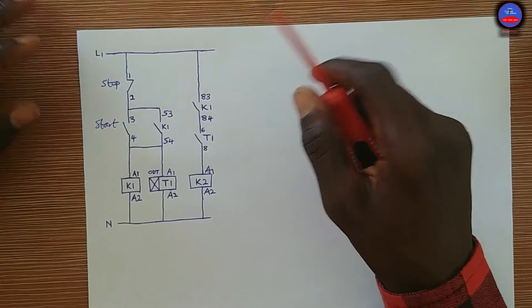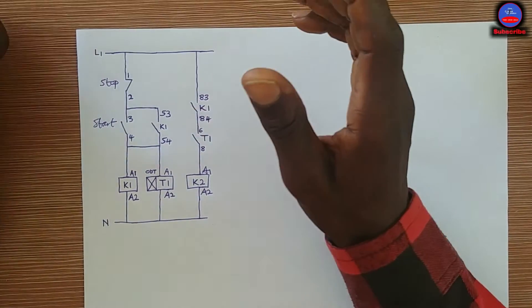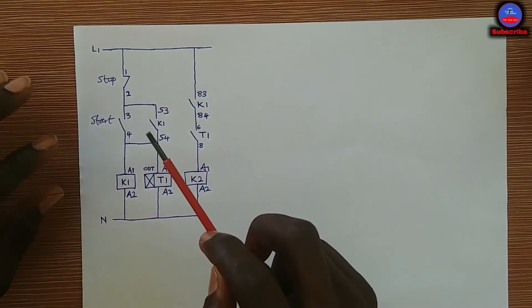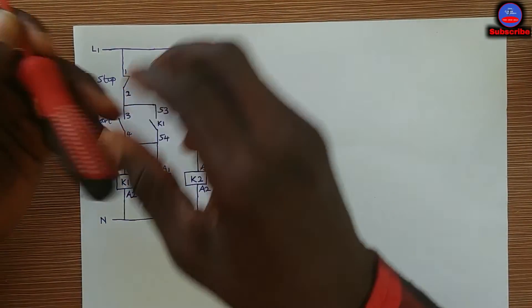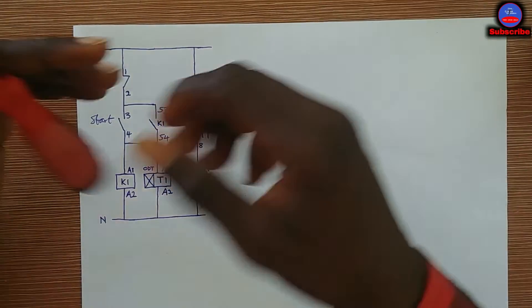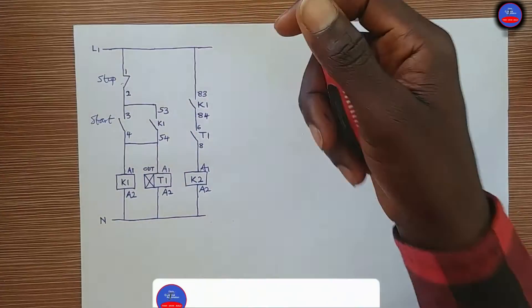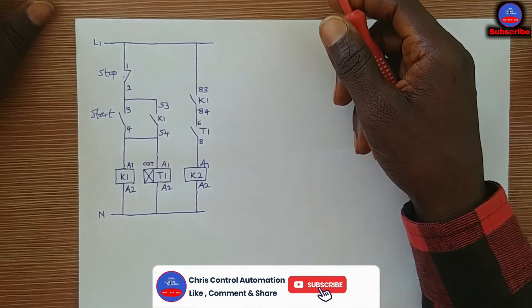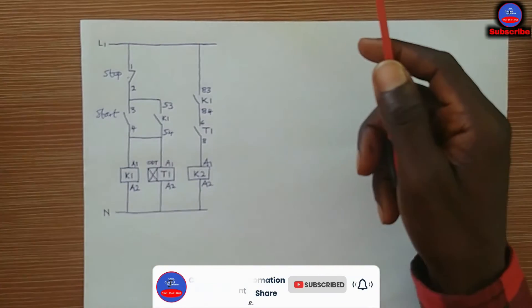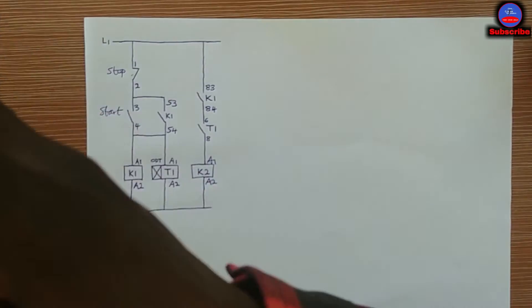Let me explain this circuit. It is an automatic sequential circuit. What that means is: when Contactor 1 (K1) energizes and is in operation, the timer will also energize and start counting. After the preset time, Contactor 2 (K2) will also come into operation and energize — so the two motors run in sequence.